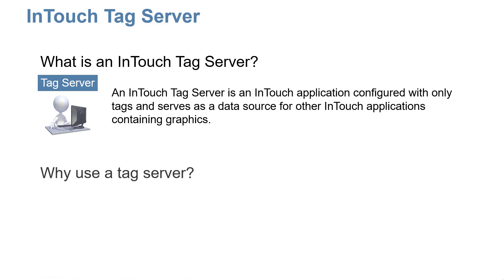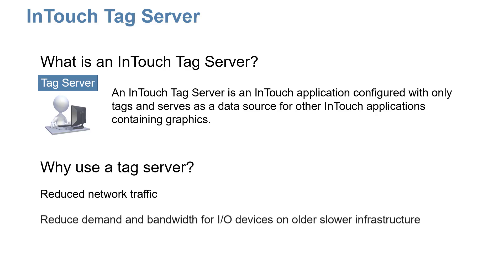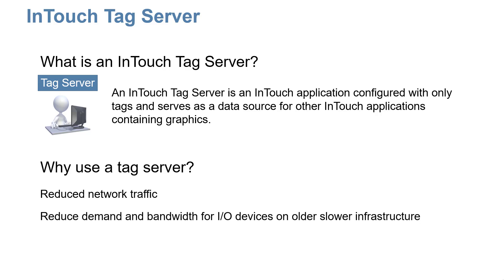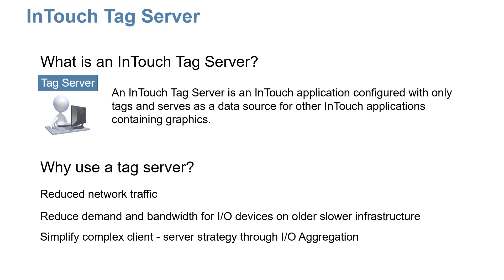Why use a tag server? You reduce network traffic, you reduce demand and bandwidth for IO devices — especially important on older, slower infrastructure — and you simplify complex client-server strategy through IO aggregation.